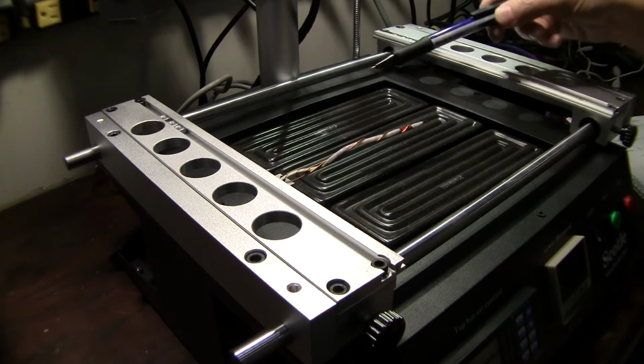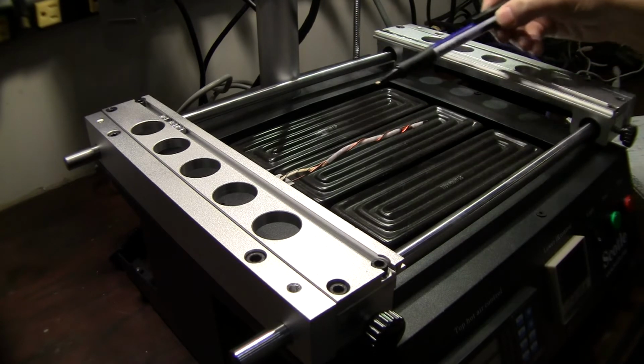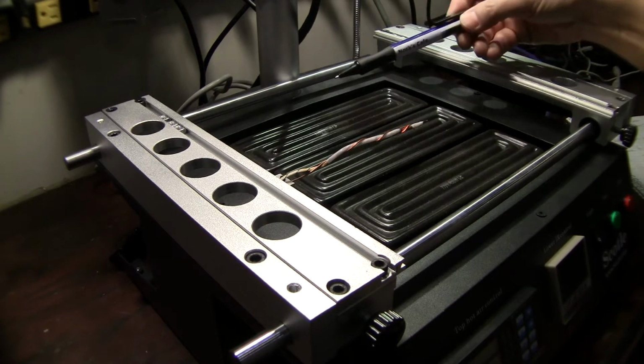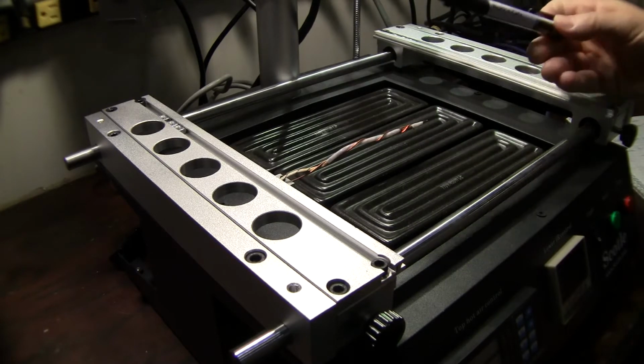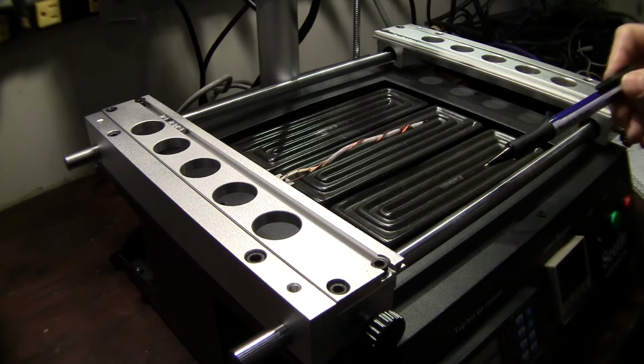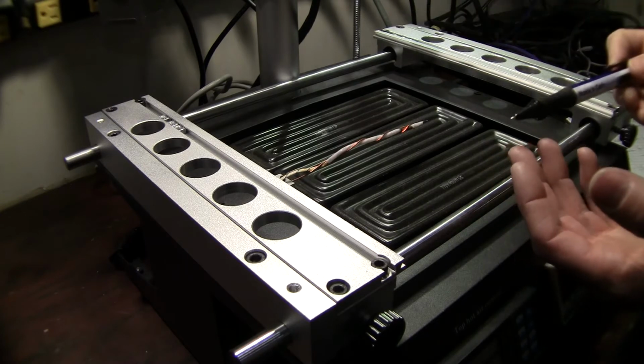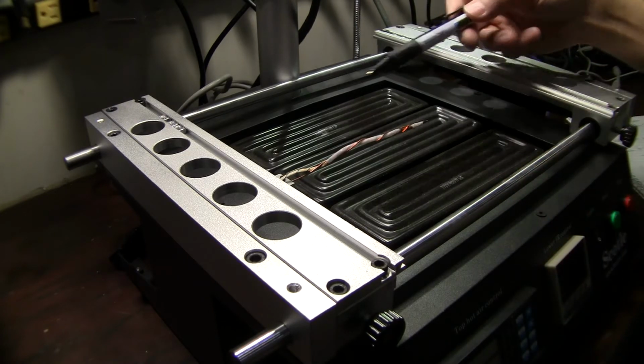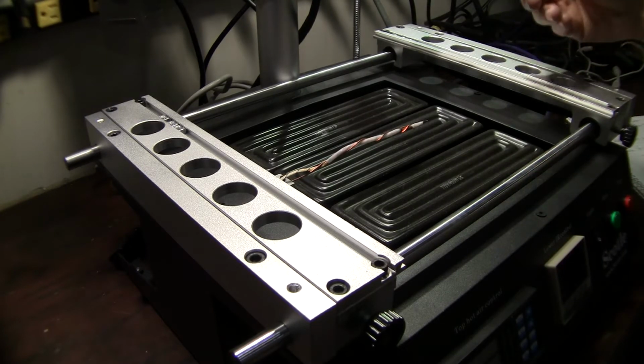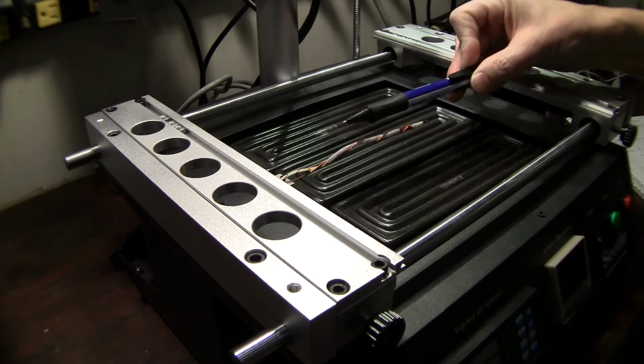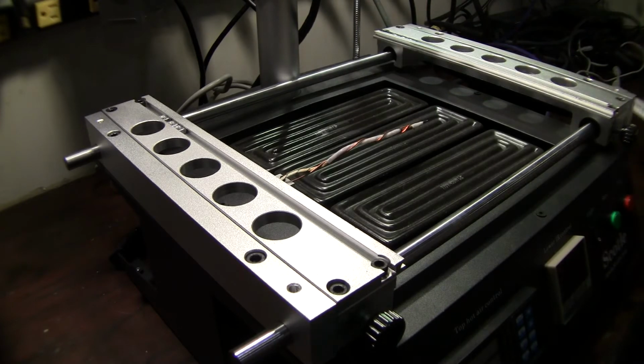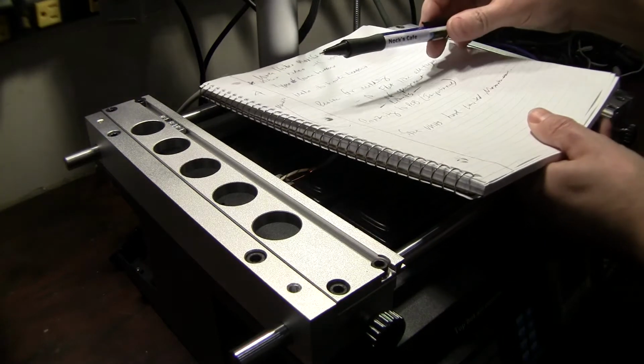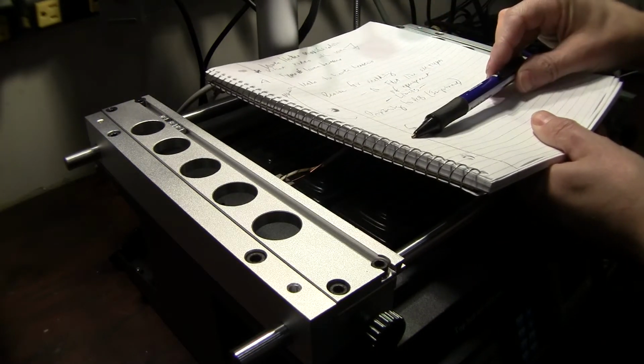If this probe thinks these plates need to create more heat, it tells them to turn on and get hotter. If it thinks they need to be cooler, it tells them to be cooler. If your probe's off here to the side, it's not going to really get a temperature of your board, and therefore it's going to inaccurately control your plates. So you have to think of it as though this probe really is what controls your board's temperature. And it does. It tells the plates how hot they need to be to make this board a temperature.